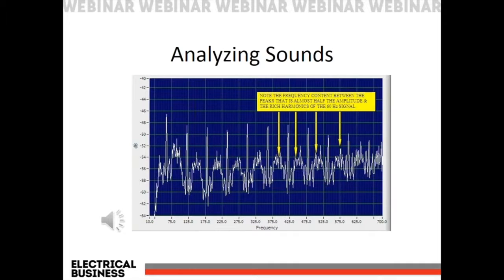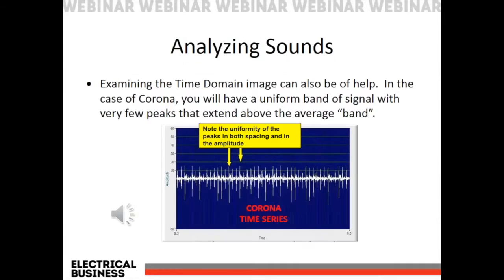All right. As we see this, we then know it's electrical, and our next step is to take it to the next level into our time domain spectrum. So we go from FFT into time domain, and we start to see and hear the same sound. Again, the same buzzing sound. This is what we're listening to. And by examining the time domain, you're going to see that we have very uniform spacing going on with some elongated negative amplitudes. From that, we can deduce that what we're listening to is corona, or seeing corona.